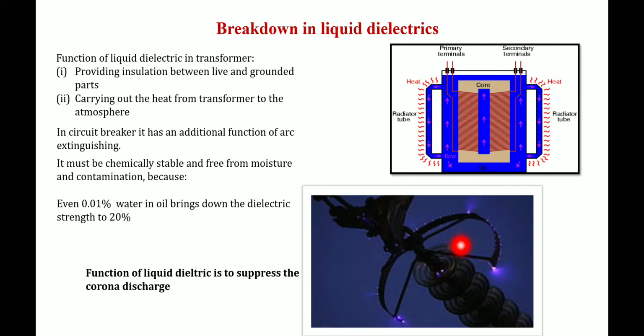That is why we often see a bluish glow around pointed metal conductors, a discharge or spark, which is produced mainly due to ionization of the air media around the conductor. In order to suppress this corona discharge, keep in mind that corona is nothing but a huge amount of energy loss. It is an unwanted side effect, a significant waste of energy for the utilities. So corona discharge should be suppressed by improved insulation media.